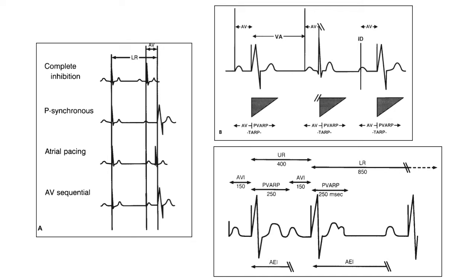If no atrial activity is sensed before the termination of the ventriculoatrial interval, an atrial pacing artifact will be delivered. That will initiate the atrioventricular interval. And if the intrinsic ventricular activity occurs before the termination of the AV interval, the ventricular output from the pacemaker will be inhibited, and this is called atrial pacing ventricular sensing. And if no intrinsic ventricular activity occurs before the termination of the atrioventricular interval, a ventricular pacing artifact will be delivered, and this is called AV sequential pacing, here illustrated in the fourth panel.